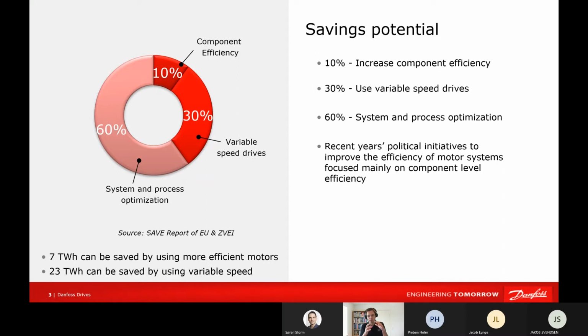Looking at the speed drive mounted on a motor at a component level - if we focus on the component, a fluid, let's say water, as a component, or the variable speed drive as a component - the saving potential is about 10%. A much higher saving potential comes from the use of variable speed drives themselves, about 30%. That means from the electrical energy we feed in, this saves energy.